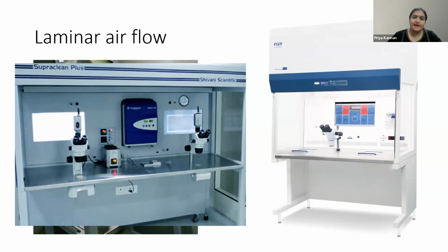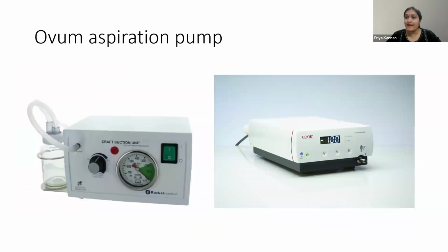So whether you want integrated or non-integrated is your choice. Whether you want with imaging or without imaging is also your choice. Whether you want one stereozoom or two stereozoom is also your choice. But if you're looking at a busy lab, or if you say, I'm buying now, but I'm going to probably expand a little bit later, but I'm happy with one stereozoom right now, I would recommend that if you have the space, buy a 6 feet laminar airflow, put in a nice trinocular stereozoom to start with, but then have the integration. That is, without this microscope, only one rod will be sticking out. Buy it along with that, so that if at all you need another stereozoom to add, just buy the stereozoom and fit it on it. It starts working. You don't have to alter your integrated stage again, or buy a new one.